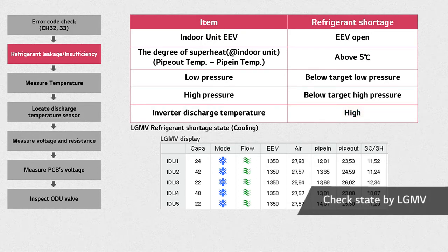Low refrigerant volume may cause excessive discharge temperature. There are two possible causes for lack of refrigerant: maybe the right amount was not charged into the system from the very beginning, or there is a leakage in the piping. Check the brazing and flare connections of the air conditioner.